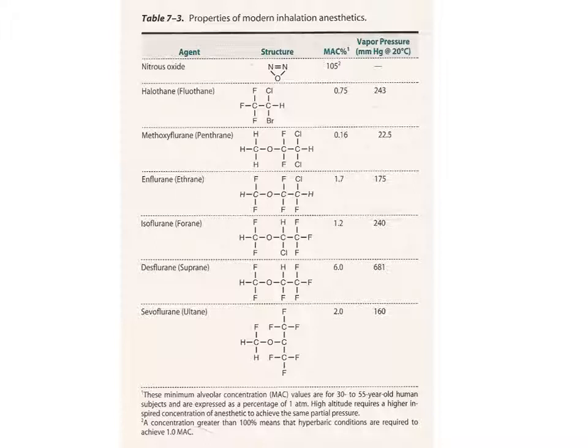The person giving the anesthetic thought they were giving oxygen, and the patient died of hypoxia because it was nitrous oxide. Somehow, behind the scenes in the wall, engineering mixed the lines up. So now they have all these systems. But you can get by any safety system. People do dumb stuff, excuse me.